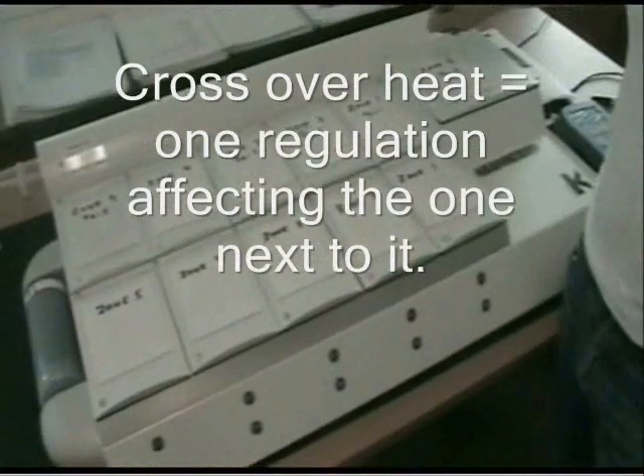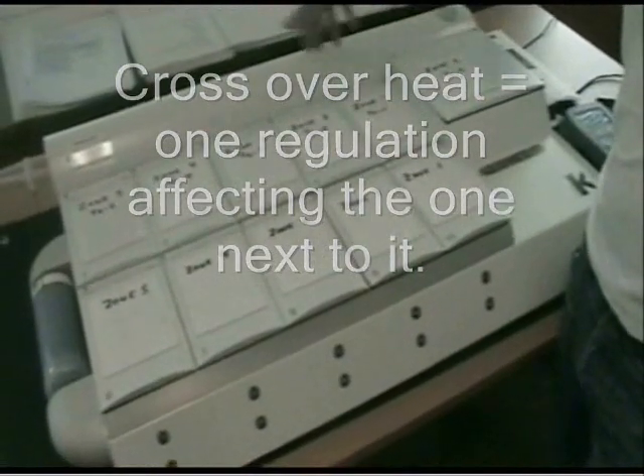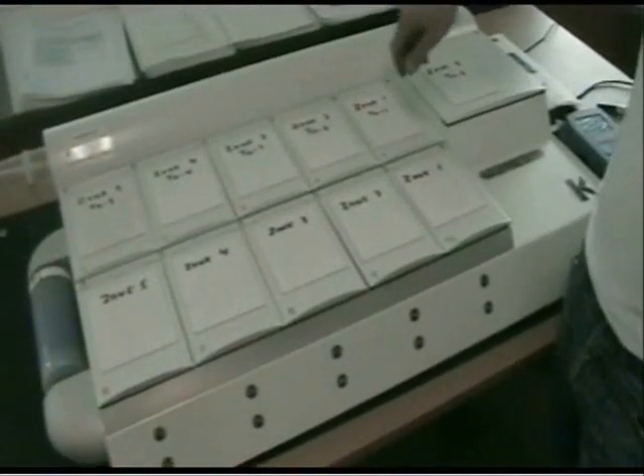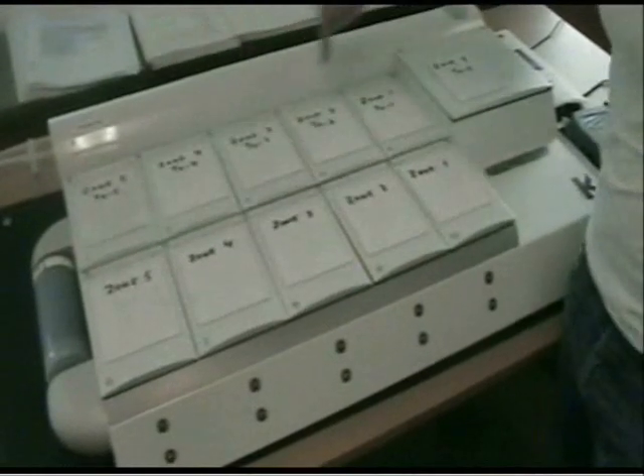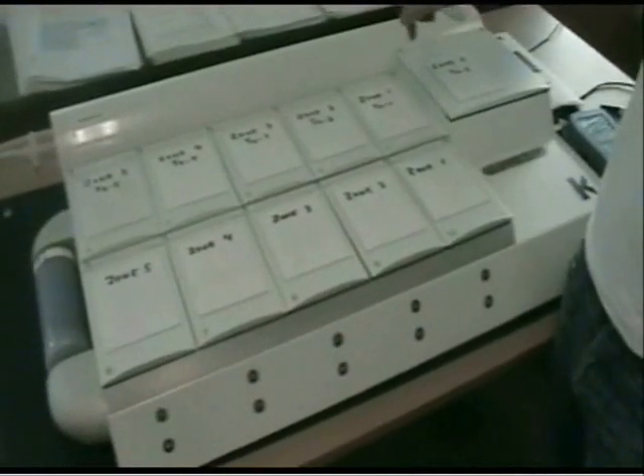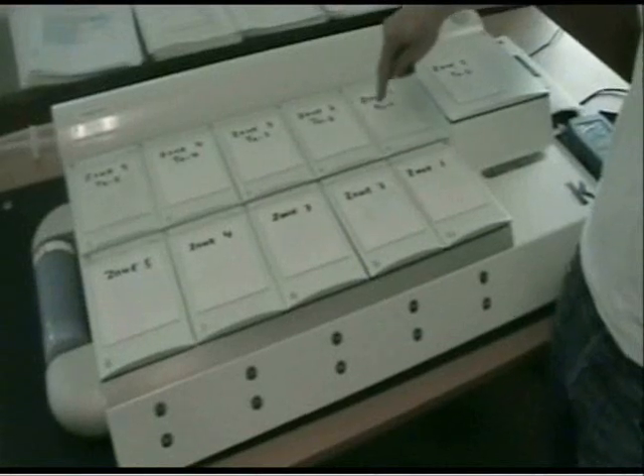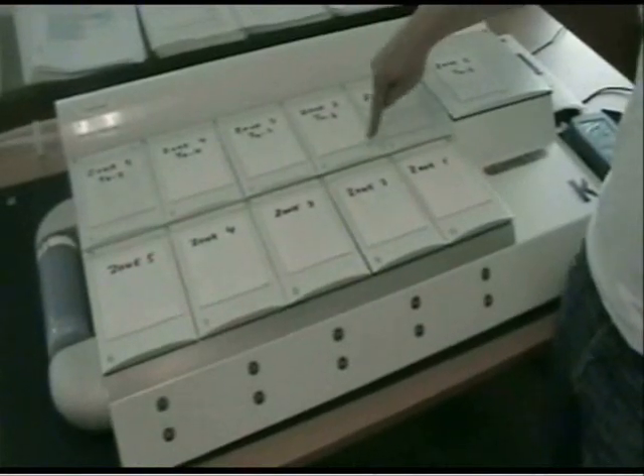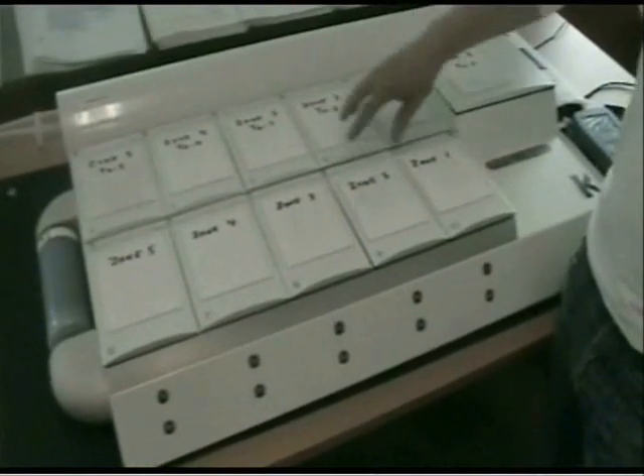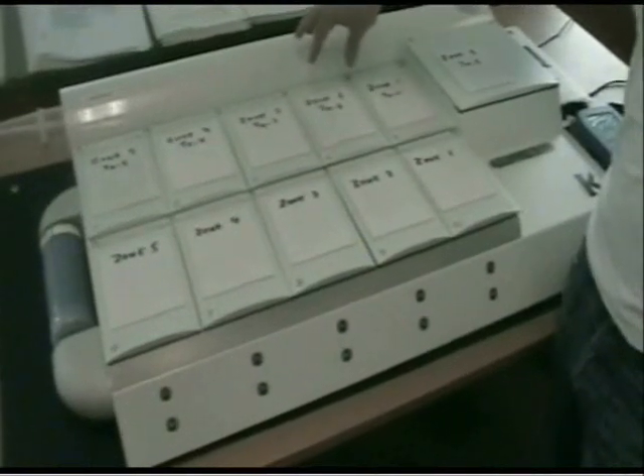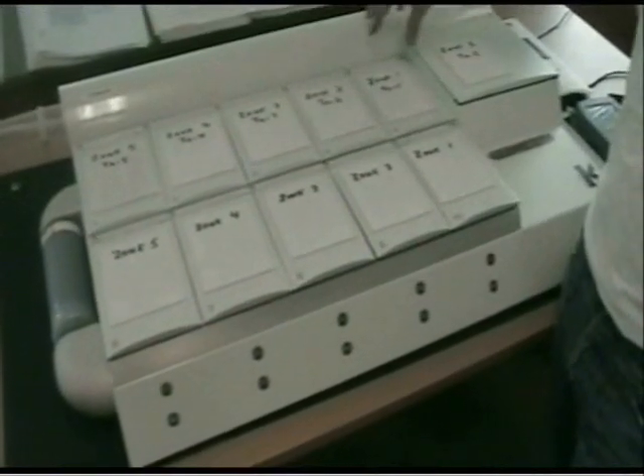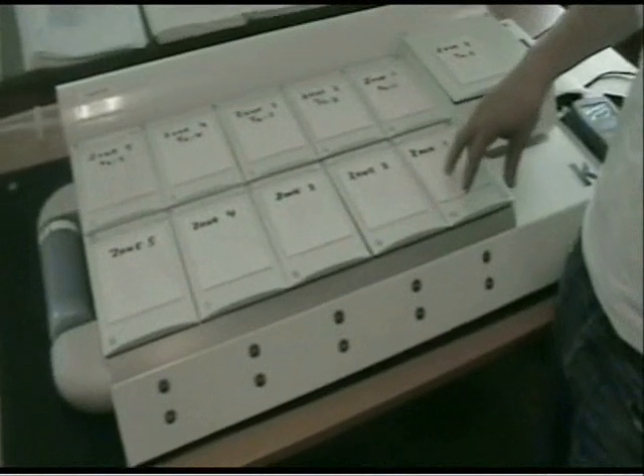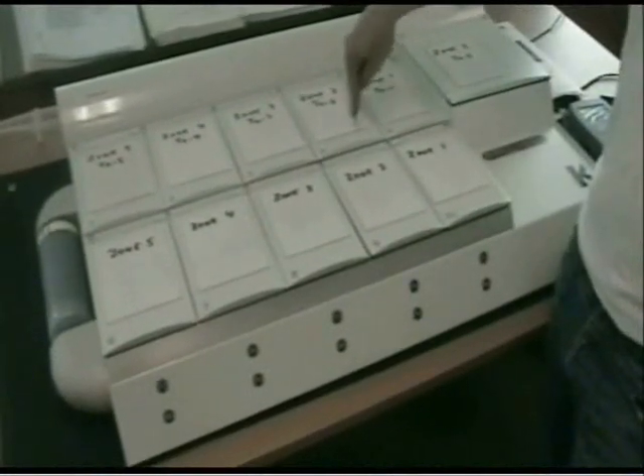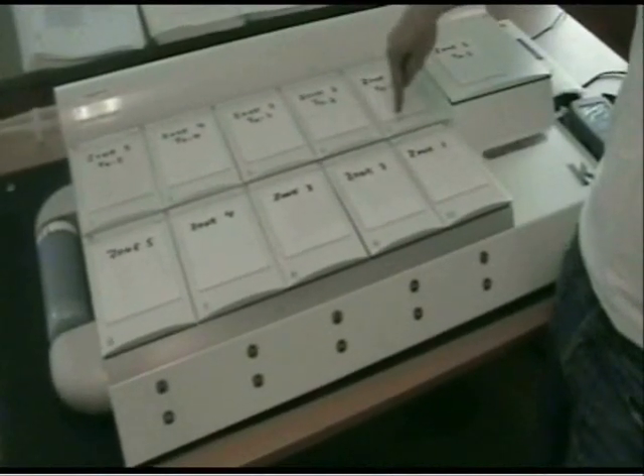In order to get a stable calibration, it's important, since all the zones and all the controllers are running on one slab of aluminium like this, to make sure that we don't have any crossover heat between the two zones located next to each other. So if zone 2 here is running, for instance, at 38 degrees, and zone 1 here is running at 37 degrees, there will be significant crossover heat between the zones.